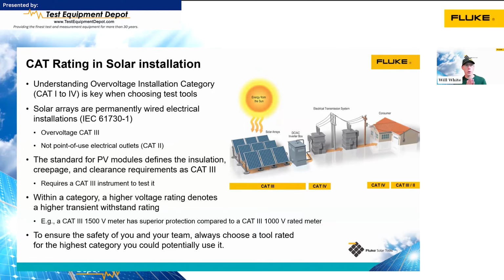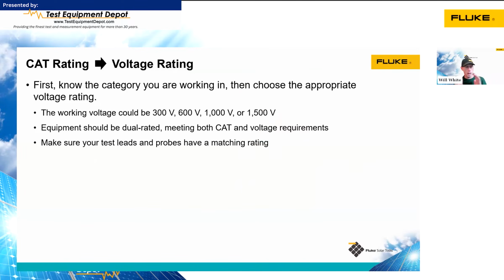It's also important to know the voltage. We're going to talk more about that in the next slide. But if we have a category 3 rated tool, as an example, a 1500 volt category 3 rated tool is going to have better protection than a 1000 volt rated category 3 tool. So we need to have a tool with at least a category 3 rating.